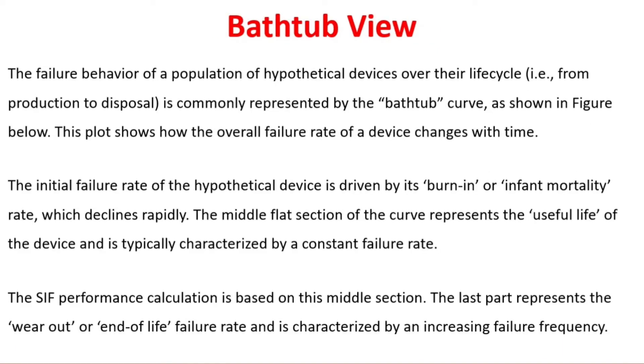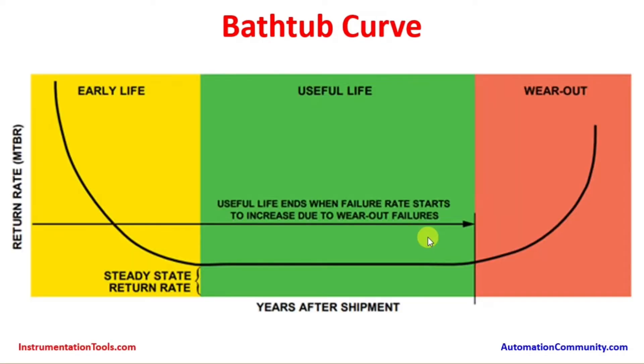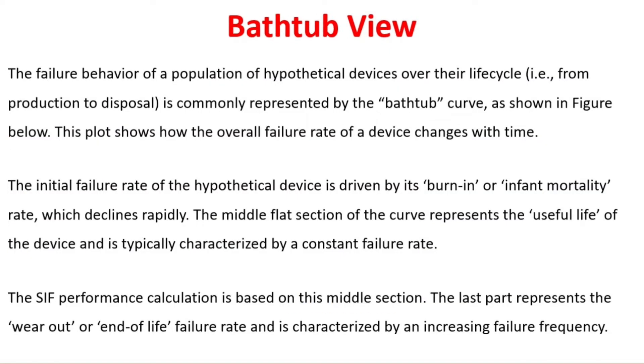The failure behavior of a population of hypothetical devices over their life cycle — from production to disposal — is commonly represented by the bathtub curve. This plot shows how the overall failure rate of a device changes with time. The initial failure rate is driven by the burn-in or infant mortality rate, which declines rapidly. This is the initial failure rate immediately after production or within the first few days of operation.